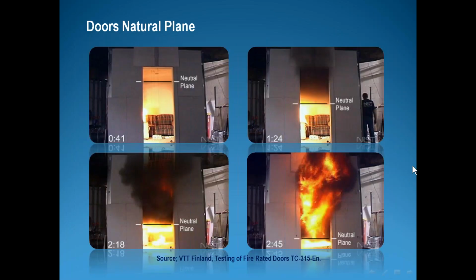Regarding the doors, all the doors which we will use inside the building, when we decide to make a smoke management system or not, these doors which separate between the hazard area and the safe area or the safe routing for the evacuation shall be tested and we must know very well its neutral plane. What is the neutral plane?